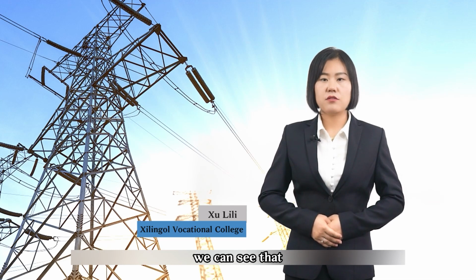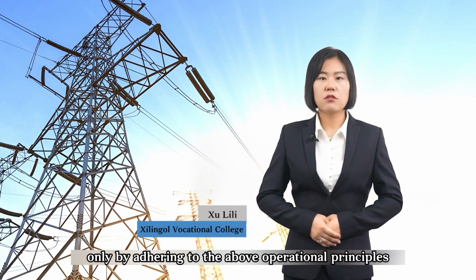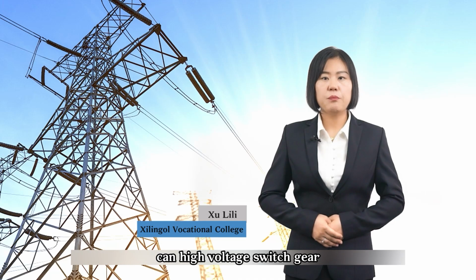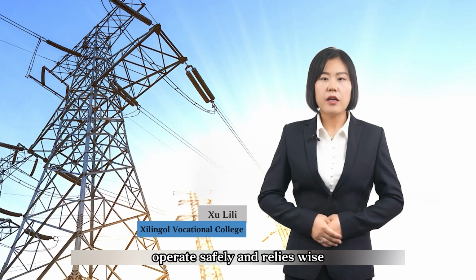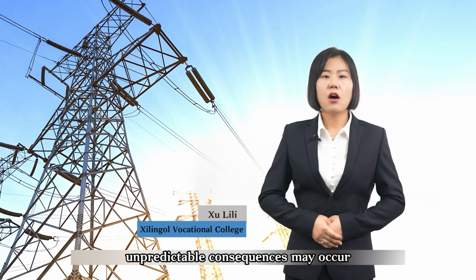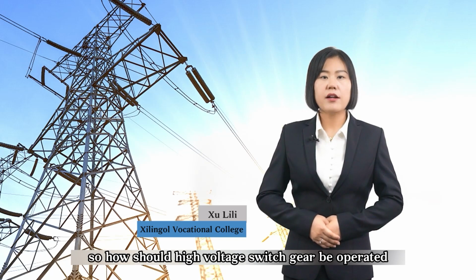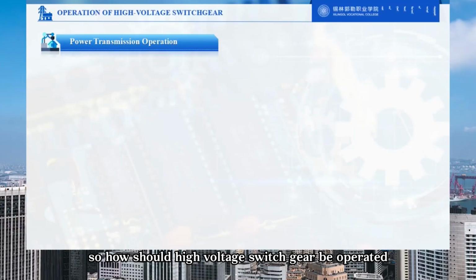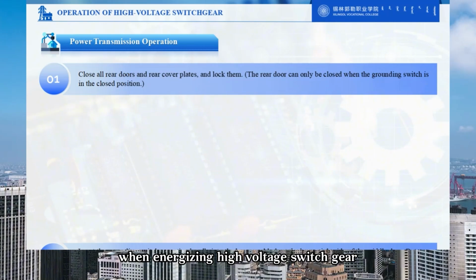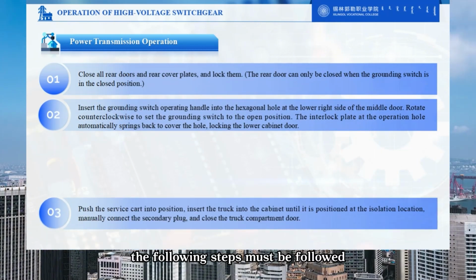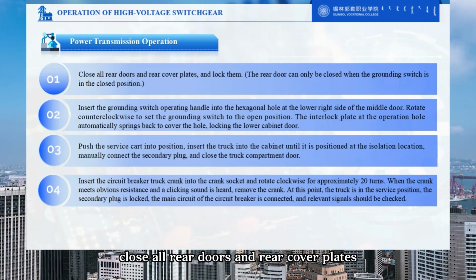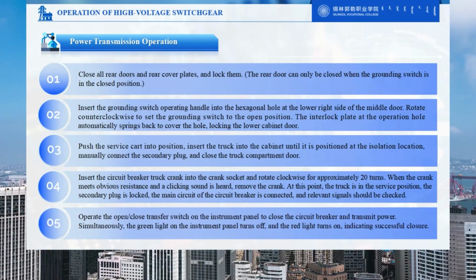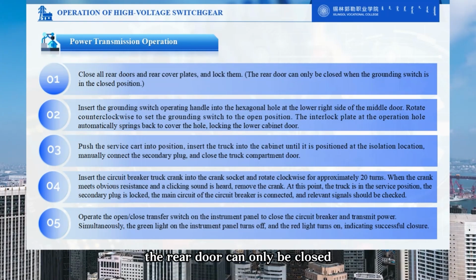From the video, we can see that only by adhering to the above operational principles can high-voltage switchgear operate safely and reliably. Otherwise, unpredictable consequences may occur. So how should high-voltage switchgear be operated? When energizing high-voltage switchgear, the following steps must be followed. Close all rear doors and rear cover plates and lock them. The grounding switch must be in the closed position before the rear door can be closed. The rear door can only be closed when the grounding switch is closed.